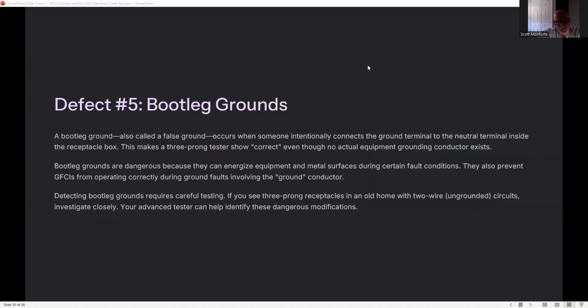Defect 5, bootleg grounds. A bootleg ground, also called a false ground, occurs when someone intentionally connects the grounding terminal to the neutral terminal inside the receptacle box. This makes the 3-prong tester show correct, even though no actual equipment grounding conductor exists. Bootleg grounds are dangerous because they can energize equipment and metal surfaces during certain fault conditions. They also prevent GFCIs from operating correctly during ground faults involving the ground conductor. Detecting bootleg grounds requires careful testing. If you see a 3-prong receptacle in an old home with 2-wire ungrounded circuits, investigate closely. Your advanced tester can help identify these dangerous conditions and modifications. At least I'm not pulling out an outlet to check what's going on there.